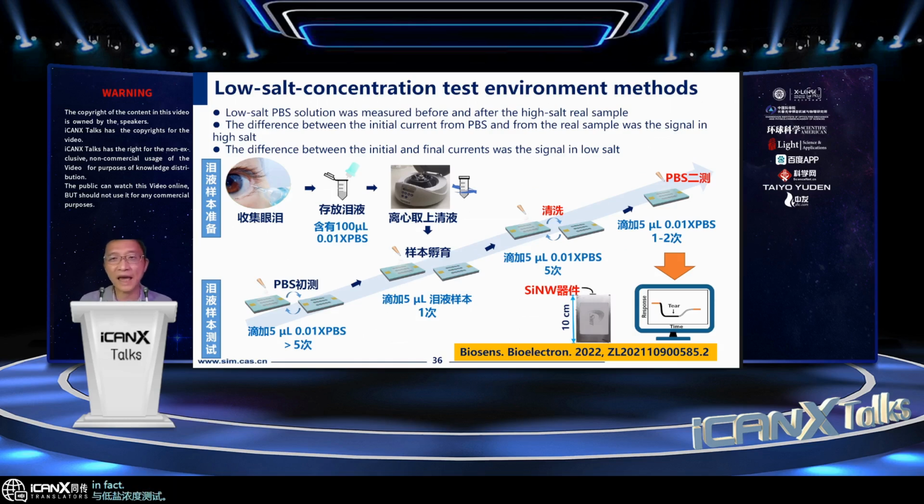In fact, we have added the second buffer concentration detection, and use it to tell the difference between the initial and the final currents to show the signal of the real target. And then we can also calibrate it in a very complex environment.